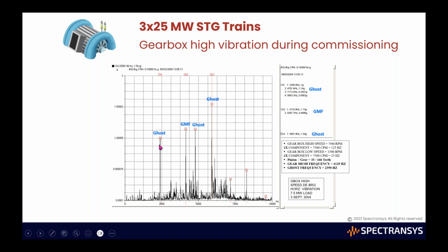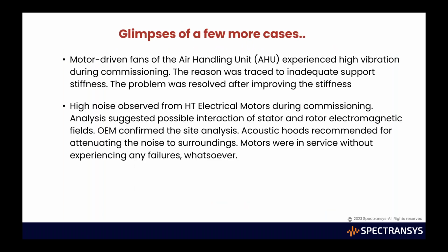Those are fundamentally coming because of the errors introduced in the manufacturing here. And finally, I have come across quite a few air handling equipment. They were large in number, and all of them had problems like inadequate stiffness support. I was involved in examining around 30 or 40 machines of various ratings, and all of them had a field unbalance problem or a structural rigidity problem.